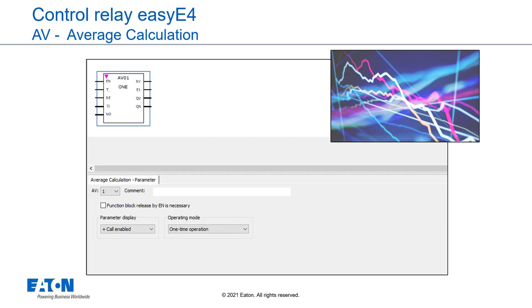easyE4 base devices provide 32 average function blocks. Averaging is a method used to smooth data series and it is primarily used for example to smooth temperatures or production data recorded over several hours or days by removing high frequency components. Please note, however, that this function block is not intended for signal smoothing or for controllers. The FT function block should be used in those cases instead.